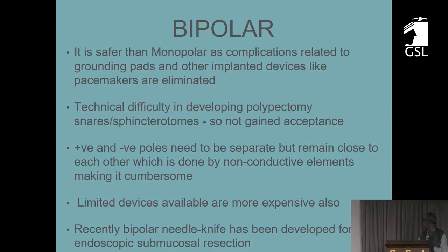There is technical difficulty in developing bipolar instruments for polypectomy and sphincterotomies, so it has not gained much acceptance in endoscopy. Positive and negative poles need to be separate, but remain close to each other, which is done by non-conductive elements, making it a cumbersome instrument. Limited devices are available and are more expensive also. Recently, a bipolar needle knife has been developed for endoscopic submucosal resections.